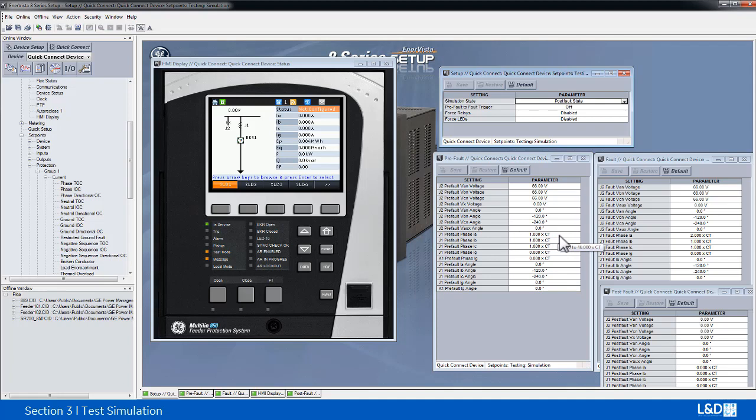For example, the phase A current, we can set this to 1. Then, if we want to test this element, we can manually turn this to 2 and click Save. So 2 times CT is applied, but the relay will not jump into the post-fault even after 3 seconds.